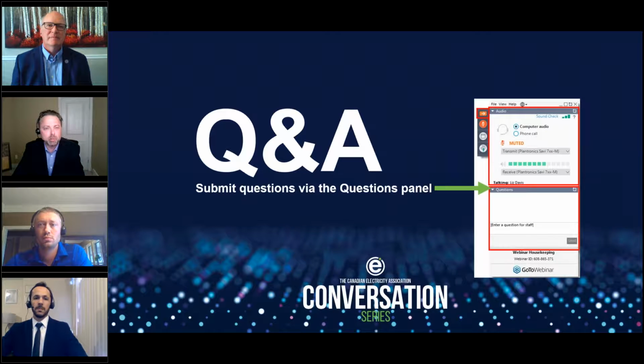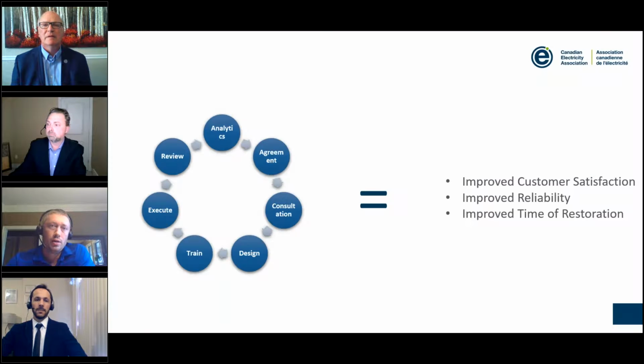I think, Aaron, our most common is the SEL 351 relay. Is that fair to say it's most common? Well, over the last year we've actually been standardizing on the 751 feeder relays. But let me expand a bit on the picture you showed with the white boxes. On the left-hand side, the first box is an engine generator set, diesel, 500 kilowatt prime mover.